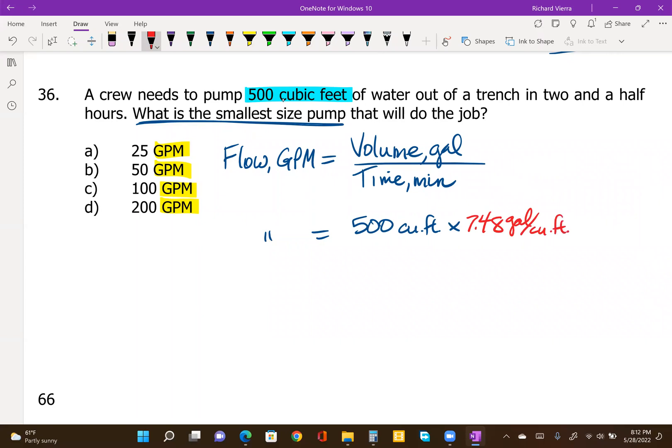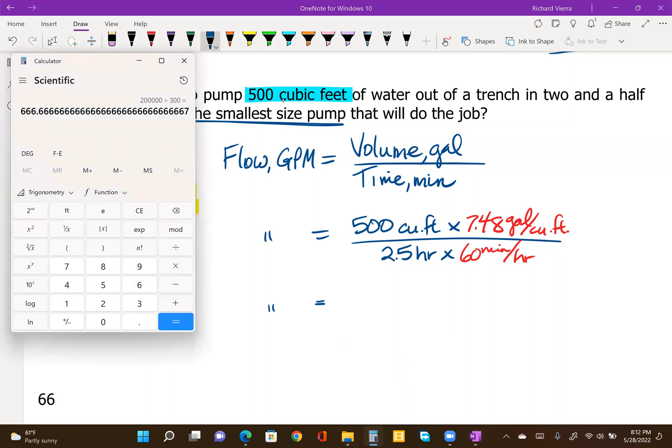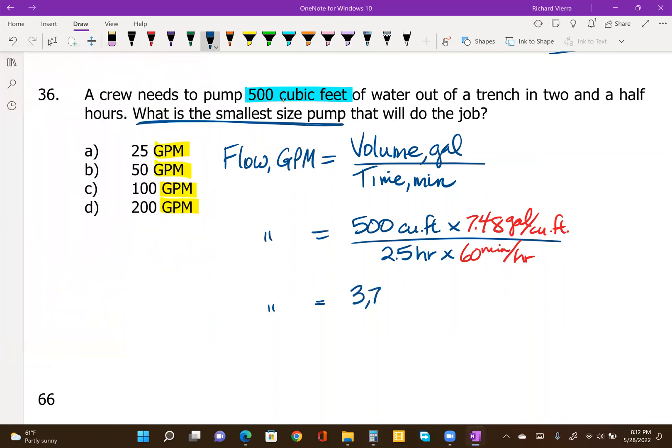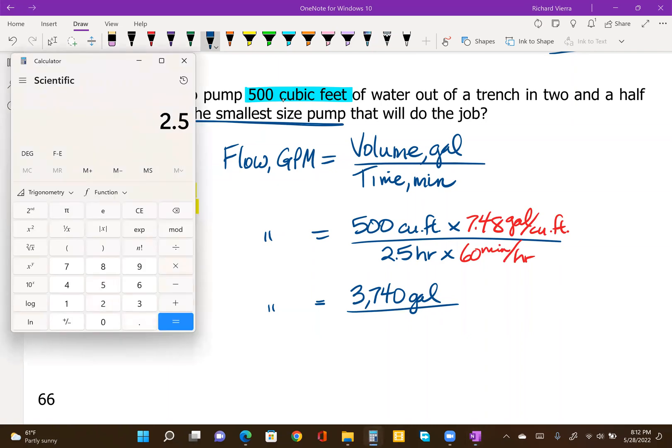And similar to the last example, we have our time period that they're wanting to have this done within given in hours. So we're going to multiply that number times the 60 minutes per hour. So let's go ahead and figure out how many gallons, how many minutes. 500 times 7.48 comes out to 3,740 gallons. So we have to pump a total of 3,740 gallons out of this trench in two and a half hours. So 2.5 times 60, which comes out as 150 minutes.